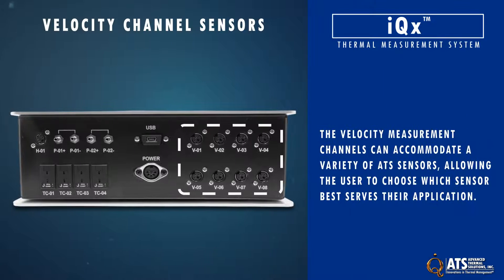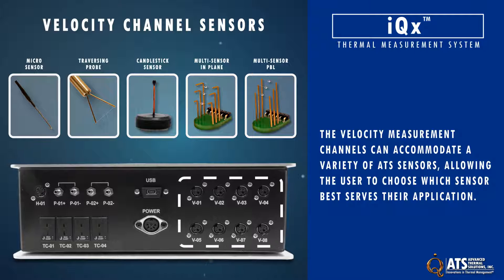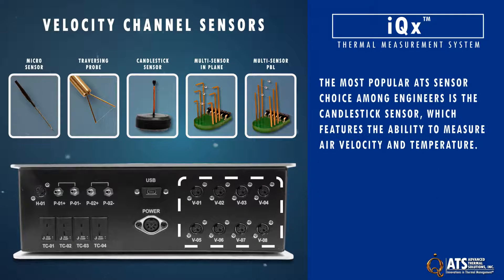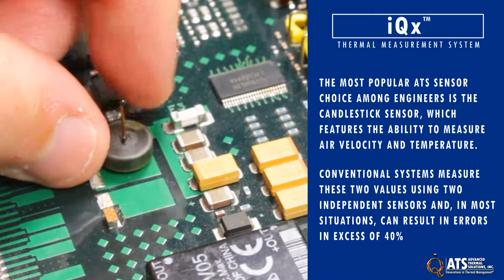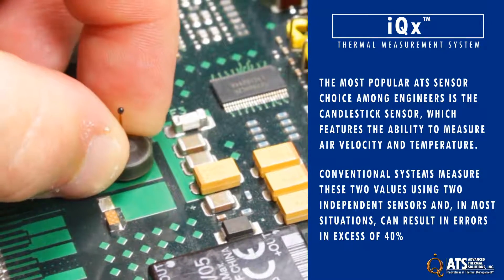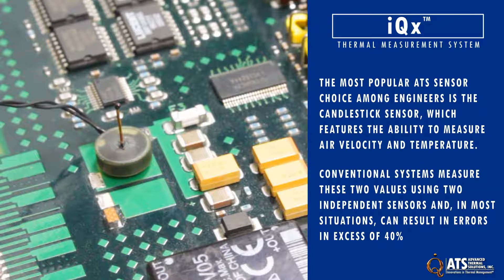The velocity measurement channels can accommodate a variety of ATS sensors, allowing the user to choose which sensor best serves their application. The most popular ATS sensor choice among engineers is the candlestick sensor, which features the ability to measure air velocity and temperature. This capability of IQX to measure airflow and temperature at the same point minimizes errors that can be introduced as a result of temperature gradients.